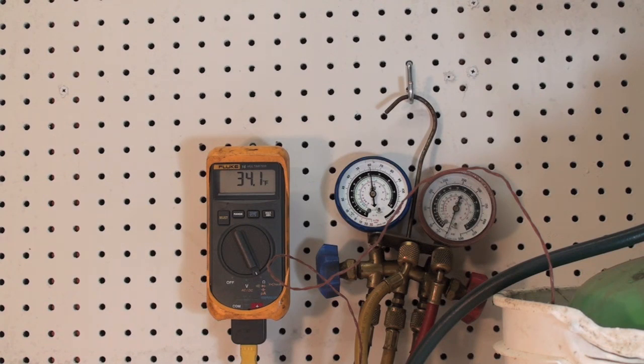So the relationship between temperature and pressure is one of our most important relationships and it does work out unless the refrigerant is contaminated with some other sort of material in it, some different gas or it's got air in it or something like that. But other than that, that is temperature pressure and it works. It is accurate for measuring what's going on inside the pipes. And that's it on saturated pressure.